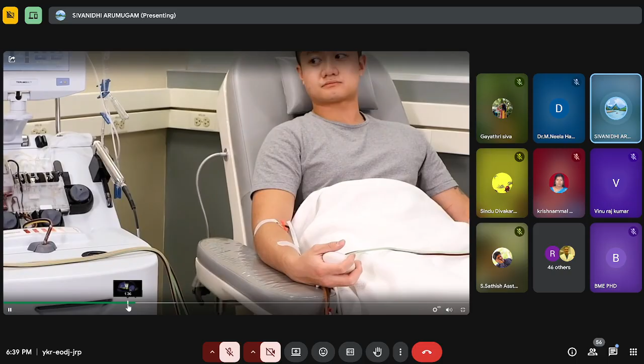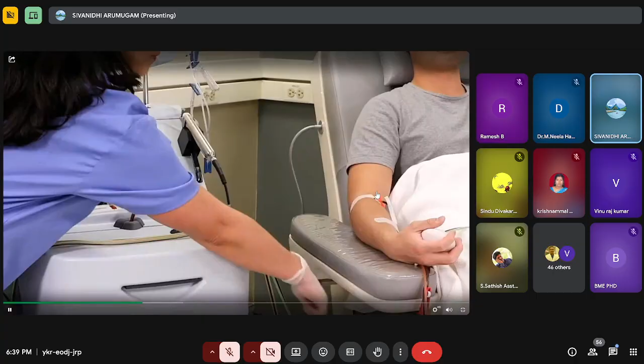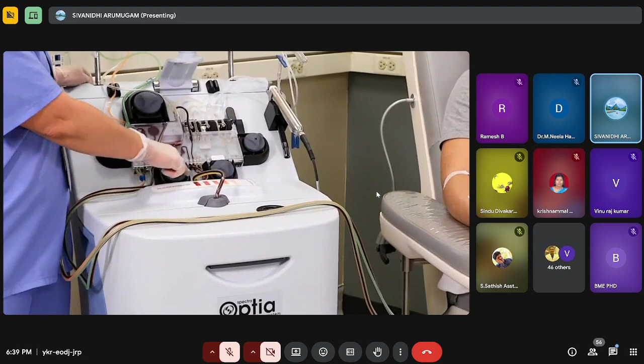You can see we are collecting inlet blood. The inlet blood is collecting here. In the channel, it begins to separate into three layers: red blood cells, buffy coat, and plasma. The centrifuge is rotating, so we are not able to see the image properly. The red blood cells are continuously returned to the reservoir and pumped back to the patient. The collect pump pumps the buffy coat, which contains the target cells, from the channel and into the chamber.